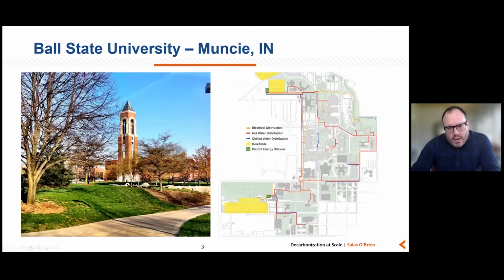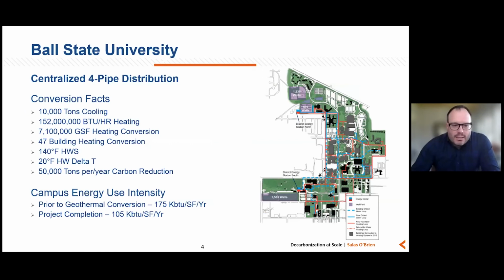The first project I wanted to talk about is Ball State University. This is a project that has been done for a period of years now and is well published in the market at this point, but it's a large district system that is 100% a ground source heat pump conversion project. So unlike the hybrid systems that were just discussed, this is 100% a conversion from coal-fired boilers feeding a district steam system to a large ground source heat pump system. Here are some conversion facts. This is a pretty big system. It's 7.1 million square feet across 47 buildings.